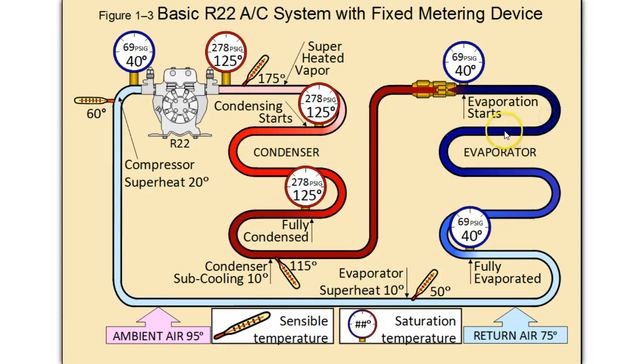As it moves through the evaporator it is picking up latent heat — a tremendous amount of heat that must be absorbed by the refrigerant for it to change state. So it changes state from liquid to vapor until it is fully evaporated. At this point it is 100% evaporated and begins to pick up superheat.